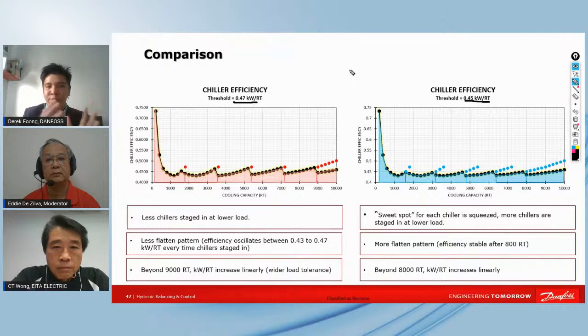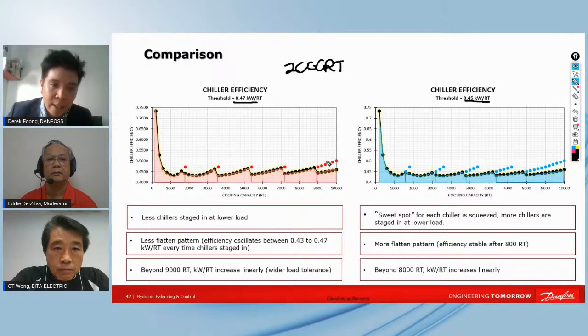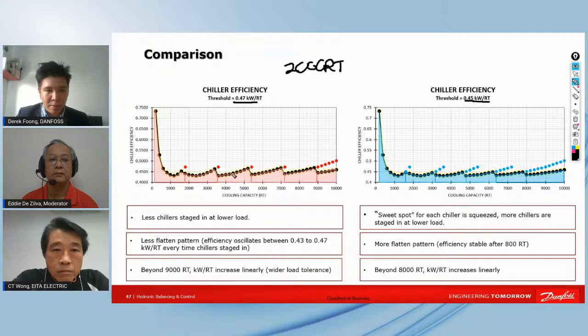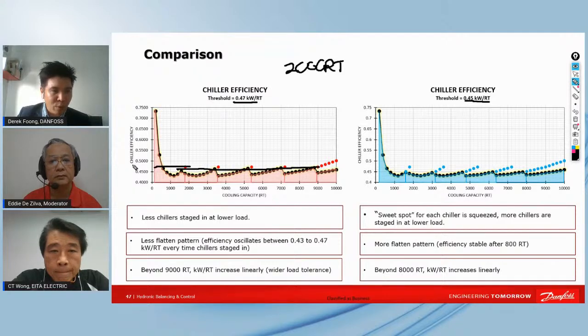So what happens if we put 5 of these chillers together? The main point here is these chillers are about 2,000 refrigeration ton variable speed chillers, and this is actually for a data center. When you put all these chillers in parallel, this is also where you define the control strategy to stage the chillers on based on load, so system load. You can see that the line doesn't go above 0.47 right here. But of course, in between you will have lower points than 0.47.